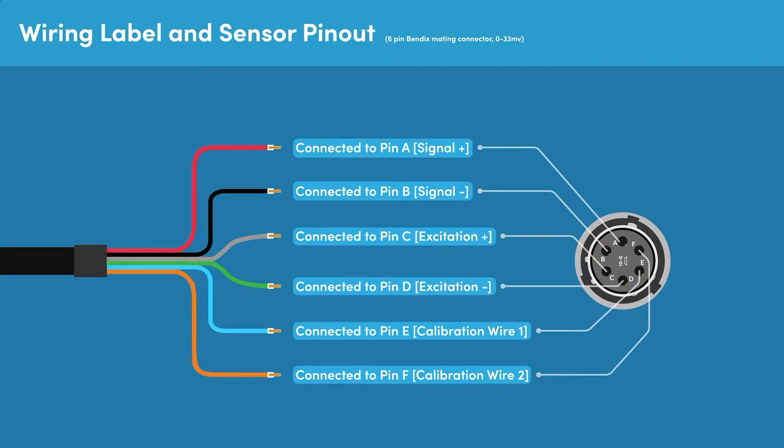The white wire is connected to pin C and is excitation positive. The green wire is connected to pin D and is excitation negative. The blue wire is connected to pin E and is calibration wire 1. And the orange wire is connected to pin F and is calibration wire 2.